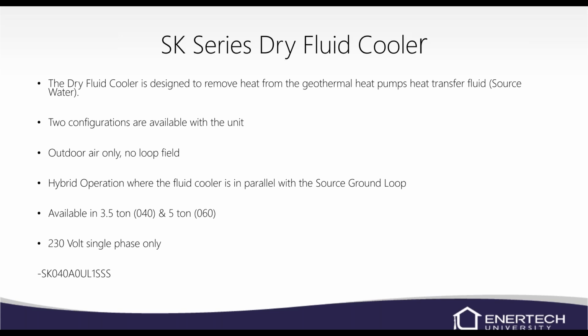On this unit, there are two configurations available. There's outdoor air only, so if you don't have a loop field, which makes this kind of nice. If you do a lot of geo, you may want to have one on hand. It's good for, let's say, the middle of the winter up in Minnesota. Somebody's propane furnace failed and they want to put a geothermal unit in. Well, the ground's frozen and you can't get a loop in the ground in January or February. You can actually hook up this SK series fluid cooler and it could be your loop, basically, which would be the outdoor air only operation. So just use outdoor air, and then you could get them by until the spring, where then you could put in your ground loop. So don't let not being able to put a ground loop in immediately stop the sale of the geothermal unit.